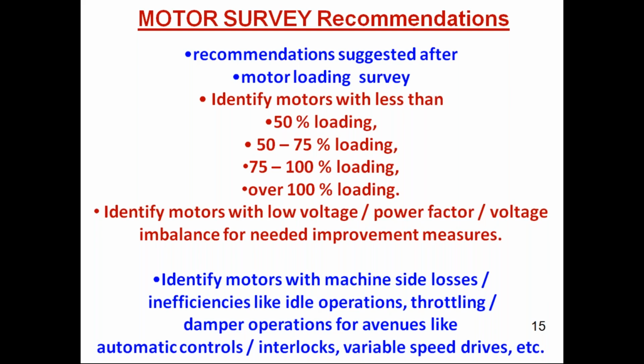An energy auditor can give two types of solutions to the industry. We can give a zero cost solution, fine tuning the process and equipment. We can also give a low cost solution, a typical example being an automatic star-delta starter. If it's a 100 HP motor, a 75 kilowatt motor, running at only 20 or 30 kilowatt, and I put in an automatic star-delta starter, the motor will start on star and then go to delta, and instead of delta it will run on star.